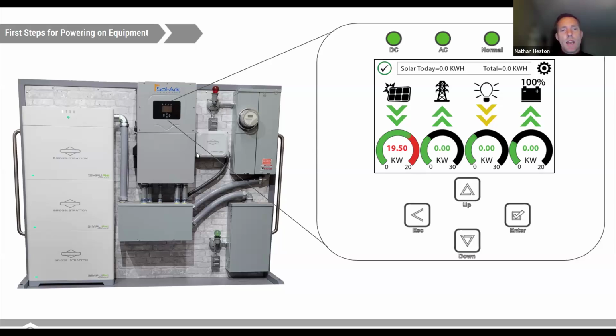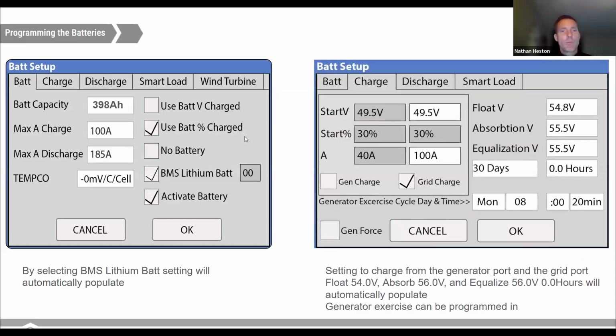You can also see that this one has an Energy Track gateway for monitoring, and that'll give you individual information about each of the battery modules on your system. It can be very useful for large battery-based systems to know information about each individual battery. Once you've enabled that battery communication with the inverter by checking this box for BMS lithium battery, with a default address of 00, and then clicking OK. OK on a Sol-Ark is essentially save. It's remember. So when you click OK, you should see the battery capacity automatically appear.